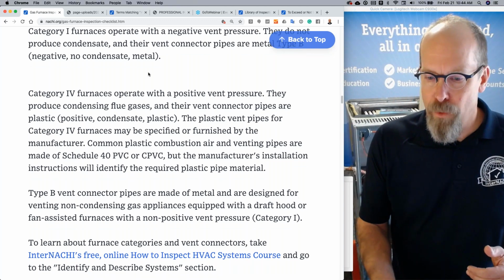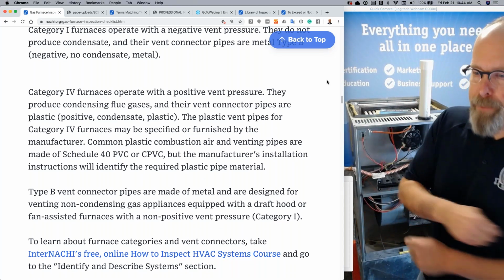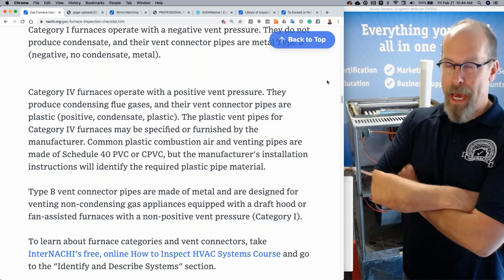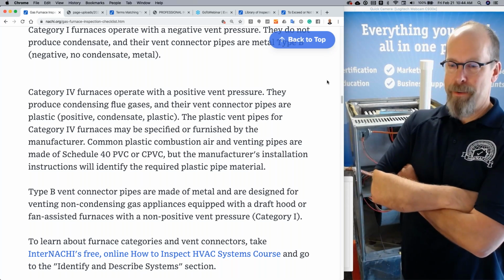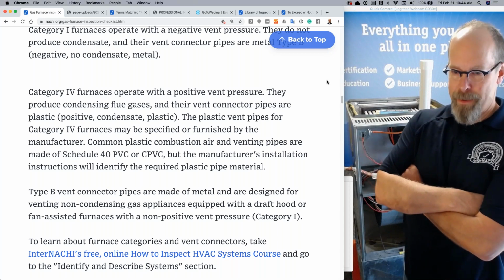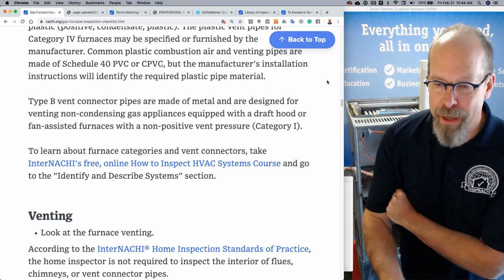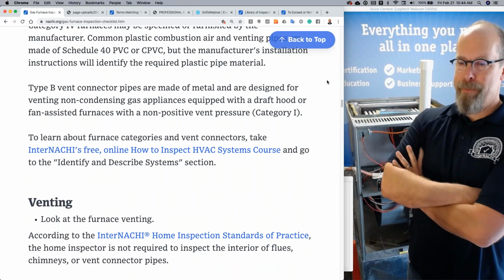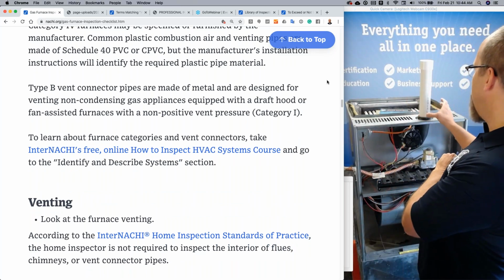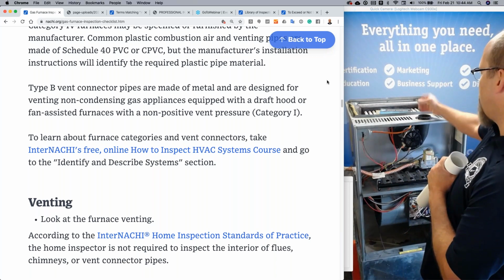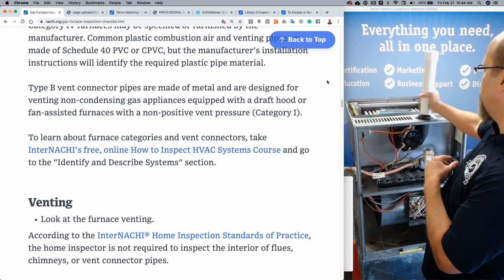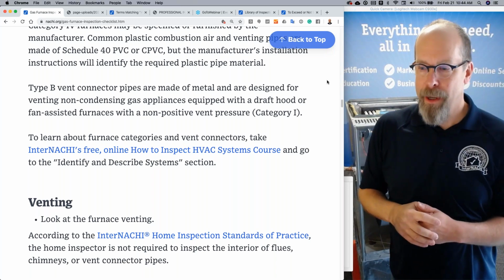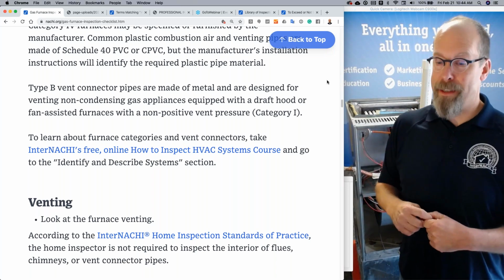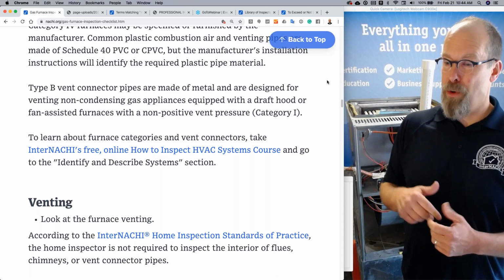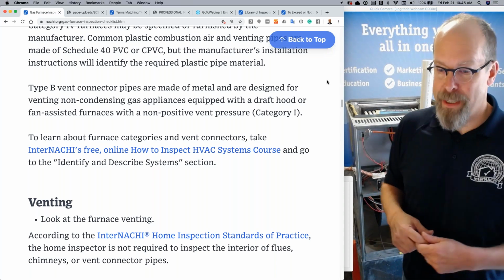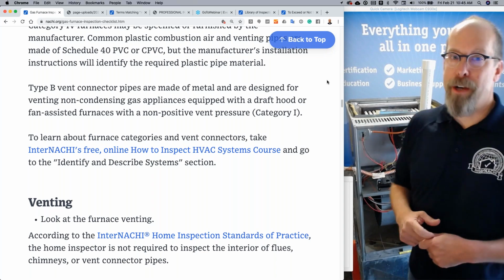Category 4 furnaces operate with a positive vent pressure. They produce condensing flue gases. They're high efficiency. Their vent connector pipes are plastic. Okay. Type B connector pipes are made of metal. So this is Schedule 40 plastic. It shouldn't be here. This should be type B metal vent pipes. And they're designed for venting non-condensing gas appliances equipped with a draft hood, that's the old ones, or fan-assisted furnaces with a non-positive vent pressure.